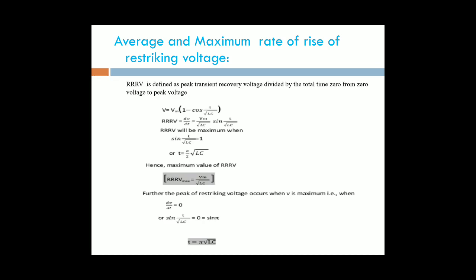Next, average and maximum rate of rise of restriking voltage. It is also called RRRV, the rate of rise of restriking voltage. It is defined as the peak transient recovery voltage divided by the total time from zero voltage to peak voltage. It is the ratio of transient voltage to the time from zero voltage to the peak voltage.